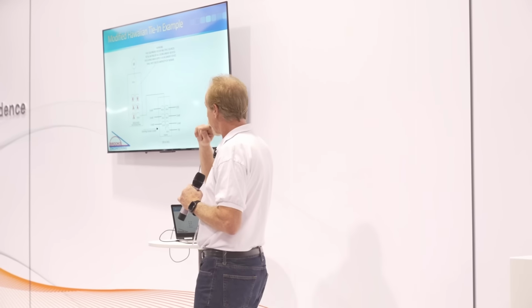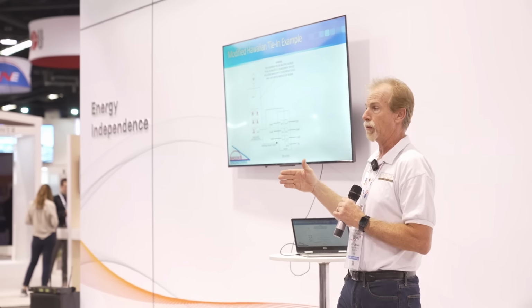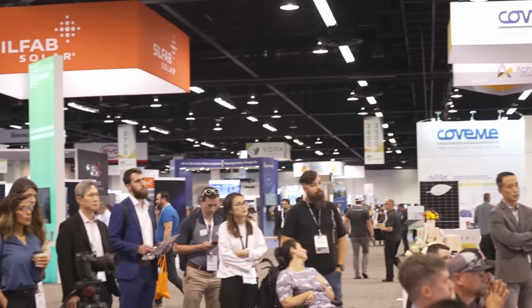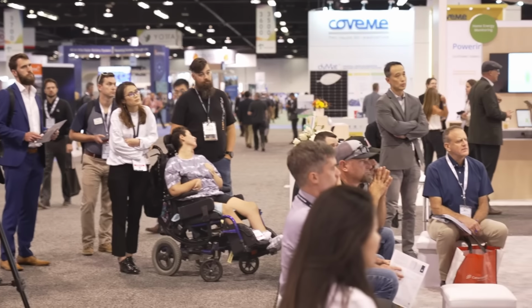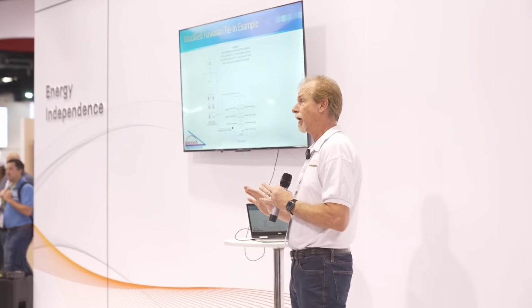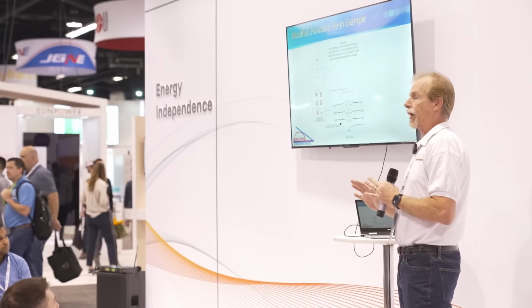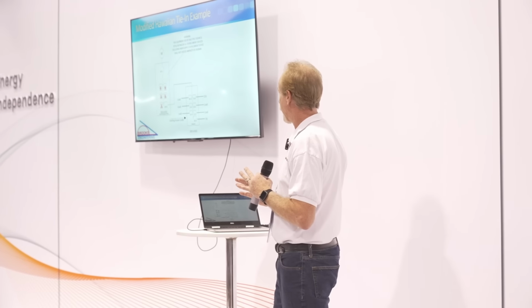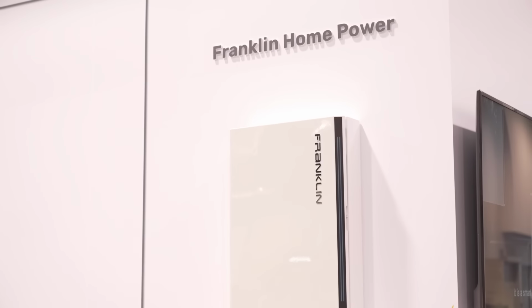So now, what if you have, in California, we have a lot of exterior service panels, right? We have all-in-one panels. All-in-one panels have always been the bane of anybody that wanted to do a supply side connection, because you cannot legally connect on the supply side of an all-in-one panel. It's impossible. Okay? There's no legal way to do it. Now, people do it all the time. There's no legal way to do it. And so when it catches on fire, not if, when it catches on fire, you'll probably get in trouble and people will get mad at you.